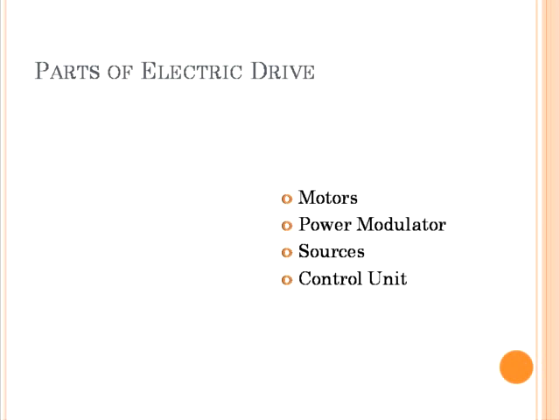Controls for a power modulator are provided in the control unit. The nature of the control unit for a particular drive depends on the power modulator used. When semiconductor converters are used, the control unit consists of firing circuits employing linear and digital integrated circuits and resistors, and a microprocessor when sophisticated control is used. When control of switching circuits is required, the function of the control unit is to provide sequencing and interlocking. Solid state relays are used, and when control is complex, PLCs can be used for this purpose.